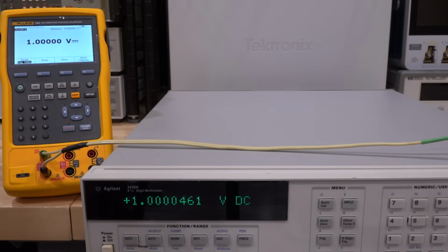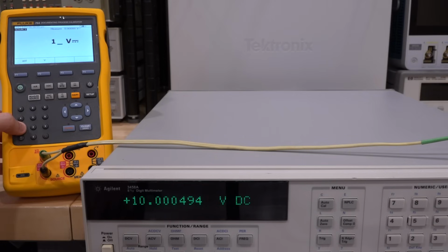It's reasonably close, and some of the calibration may be off, of course, but nonetheless, it seems to be measuring voltage correctly. So here's 5 volts, and 5 volt looks good as well. Let's try 10 volt, and 10 volt looks good. Yeah, that's pretty good. Let's try something small, 10 millivolt, and it should measure. There you go, 10 millivolt, very good. 1 millivolt. And that's also 1 millivolt. So the voltage definitely works.